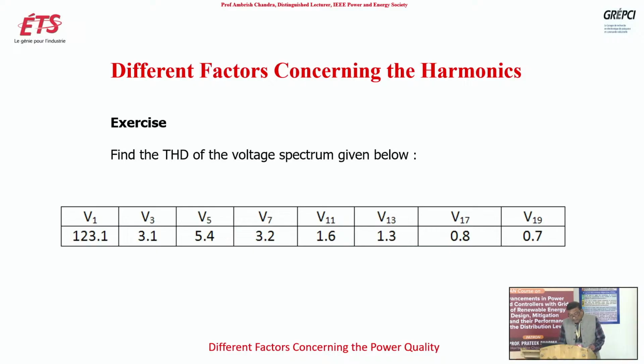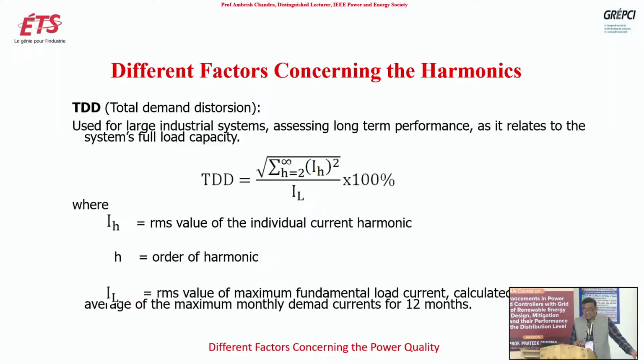Another important thing is the TDD. As a power quality engineer, I have seen that in most papers they don't mention TDD, right? THD is basically for a smaller system like ours, not in megawatts or a big system, whereas TDD, total demand distortion, is used for large industrial systems, assessing long-term performance as it relates to the system's full load capacity. THD is used for smaller, less complex systems. So for the small systems we work on in our labs, THD is good enough.